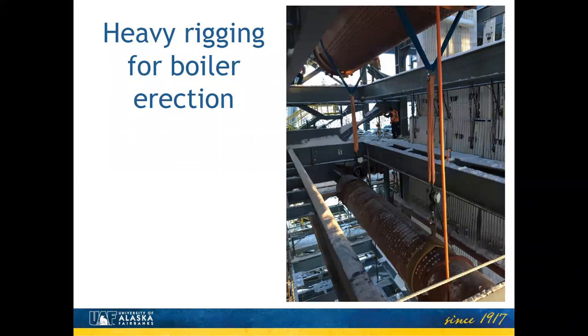Yeah, there's a lot of substantial rigging that goes on in a building like this to get all the heavy components in place. This is hoisting the steam drum and mud drum, the main components in the boiler, up into their final position at the top of the building. And one of the cost saving measures that we came up with, instead of mobilizing a crane large enough to pick up these 120 tons worth of material that's dead center in the building and would require a huge crane boom to reach out and over to them, we rented strand jacks, which take a bundle of cables and just pull them through inches at a time to hoist loads like this. And that was substantially less cost to mobilize than a large crane, right?